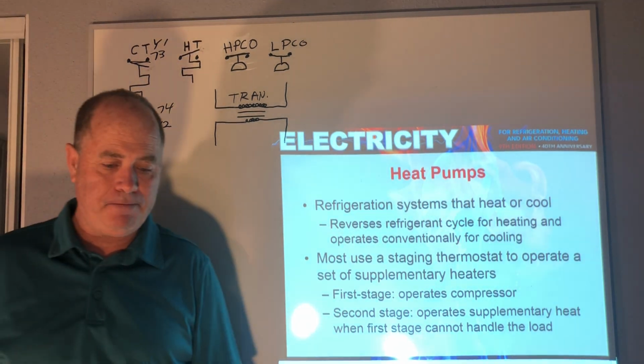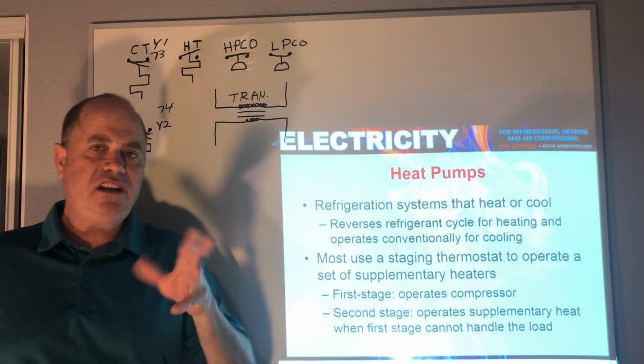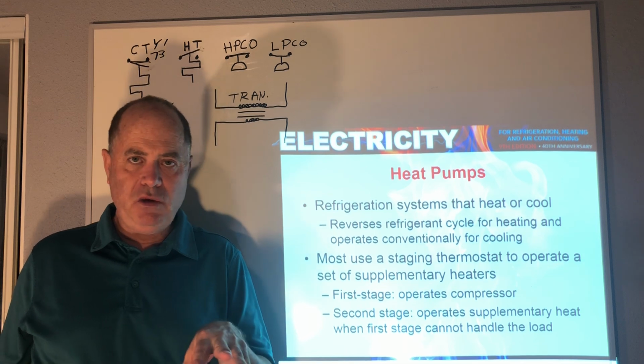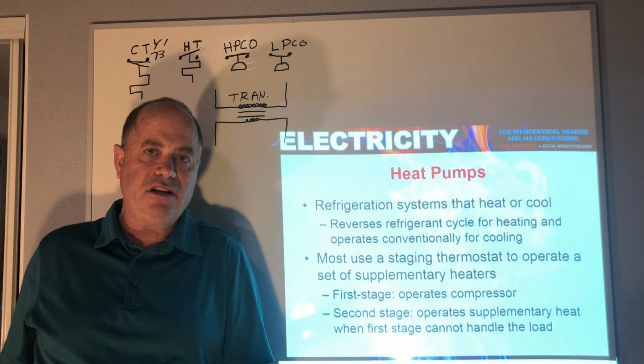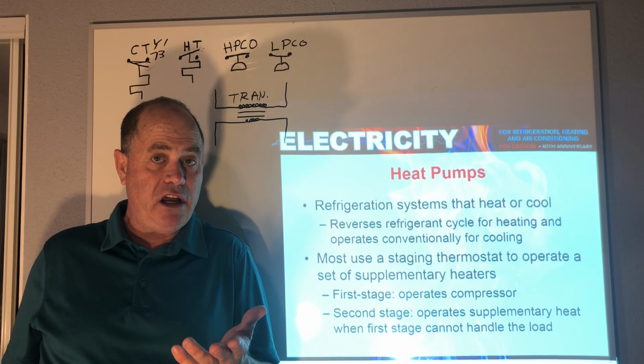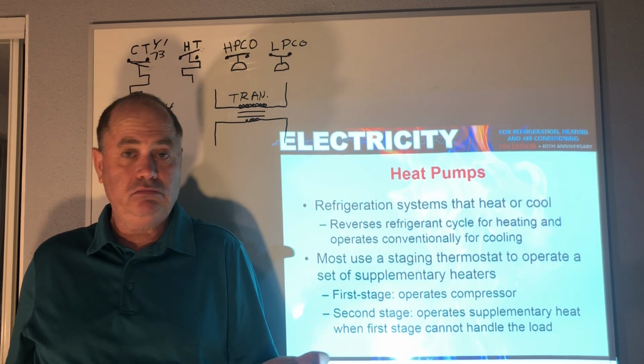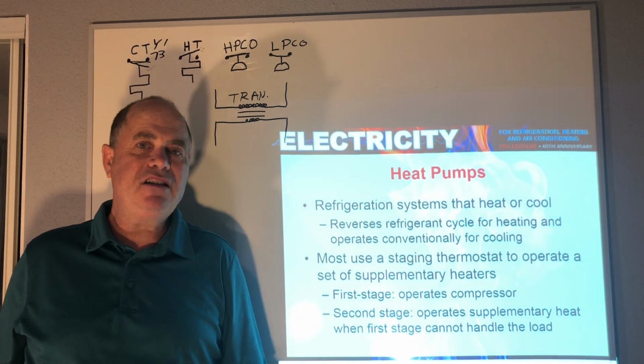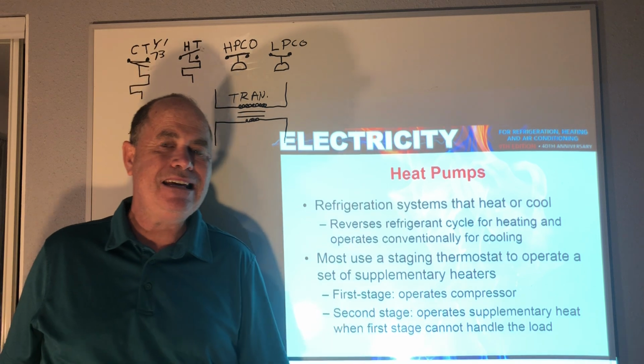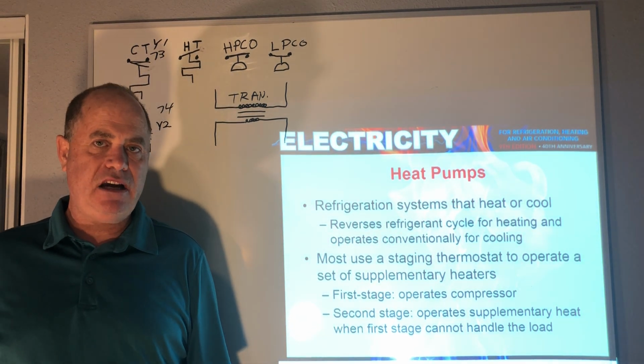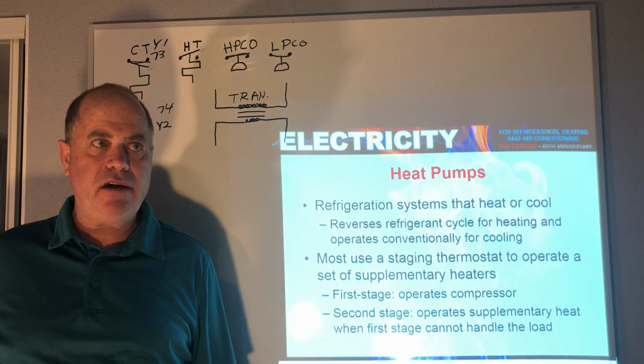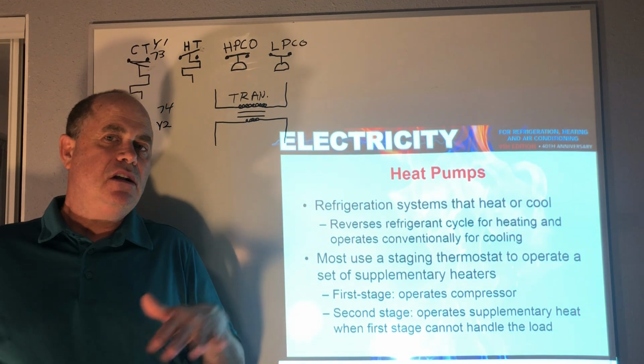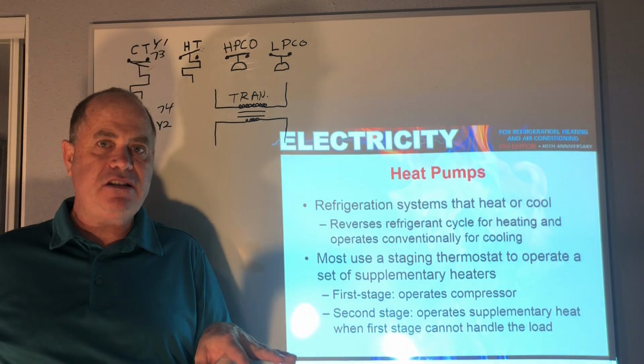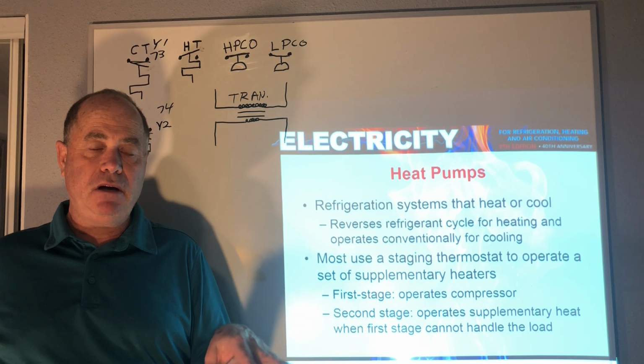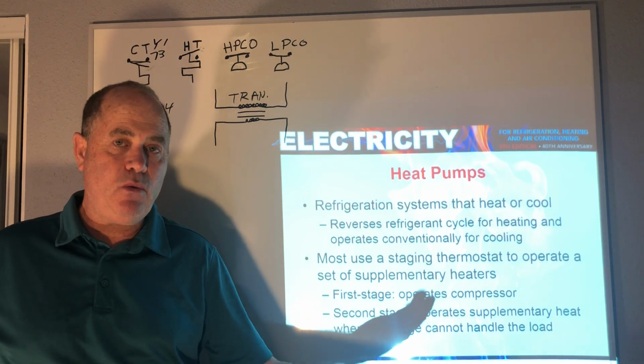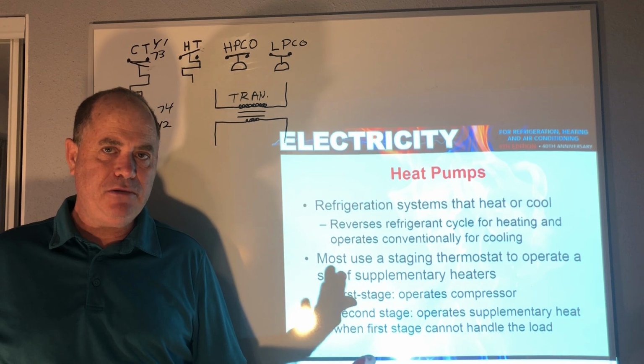So we can still on the heat pumps have Y1 and Y2 as you normally would with cooling, but for heating a lot of times you'll have W1, which is traditional refrigerant heating with a heat pump, and then W2 might be electric strip heat downstream in the supply air, which if it got really cold outside and you don't have enough heat outside to really heat the structure, you bring on some electric heat, which is a little more expensive than running your heat pump per BTU, and you'll add heat that way, supplemental heat, and that might be your W2.